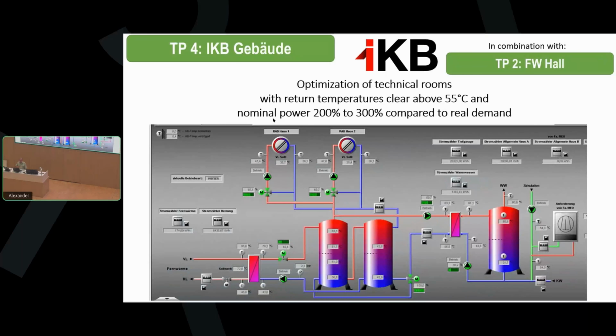Another point with IKB, the utility in Innsbruck, and that's one of the core points from my side also, to optimize the technical rooms, the consumers. So at the moment in the networks, we very typically have very high return temperatures, very inefficient. Also the heat losses of networks are very often very high. So very often we have much more than 55-degree return temperature.